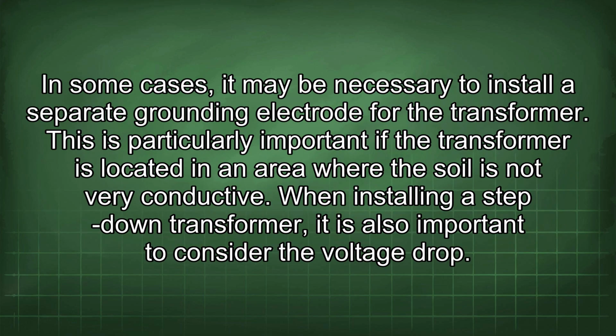In some cases, it may be necessary to install a separate grounding electrode for the transformer. This is particularly important if the transformer is located in an area where the soil is not very conductive. When installing a step-down transformer, it is also important to consider the voltage drop.